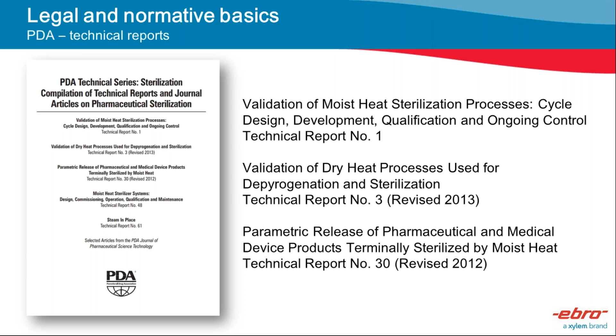Sterilization. This is where we always start with the validation. And in the medical field, we can have different sterilization settings, because they are dealing with different kinds of procedures. For example, for spores that are generated by lower creatures like bacteria, fungi, protozoa, and so on and so forth, they have a specific approach in sterilization. But in most cases, most of these microorganisms can be addressed using a sterilization setting of 121 degrees Celsius or 2 bar in specific minutes.